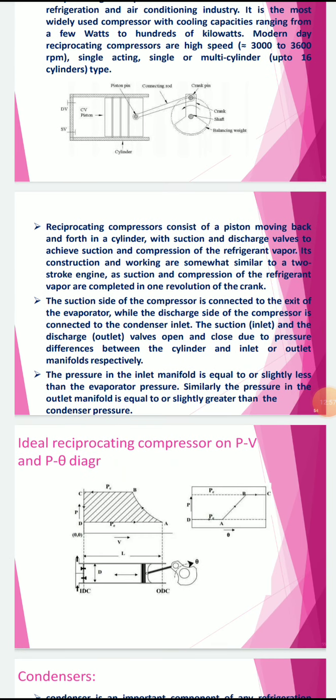and thereby in compression we have two types: wet compression and dry compression. Wet compression is not suggestible because of the vapors. If you have the dryness fraction or the wetness fraction of the vapors, that leads to damage to the compression units, like cylinder walls may get damaged. That's why it is not preferable. Whereas dry compression, the vapors which are coming out from the evaporator are suggested to be dry in state.